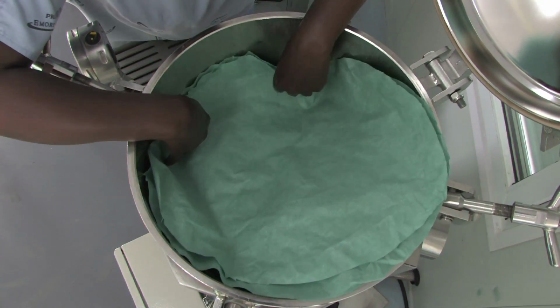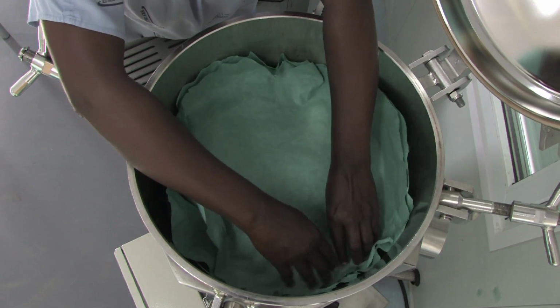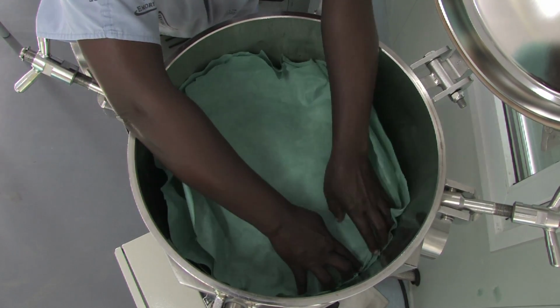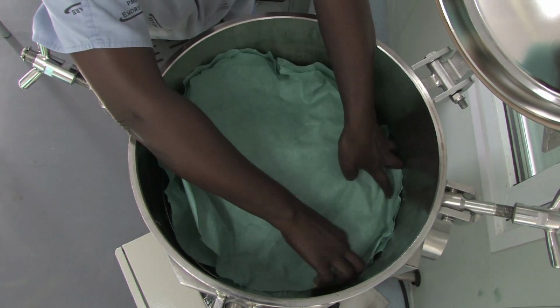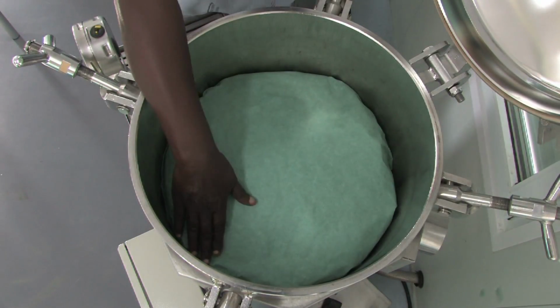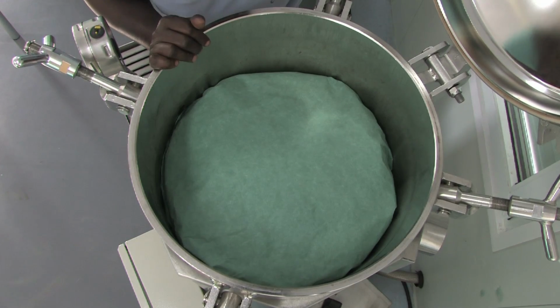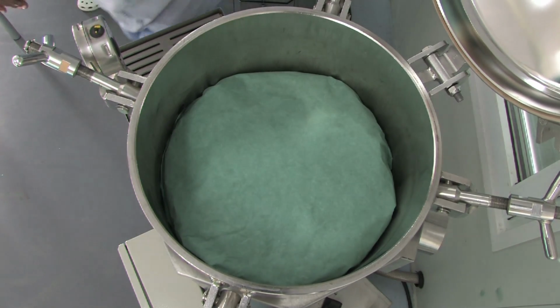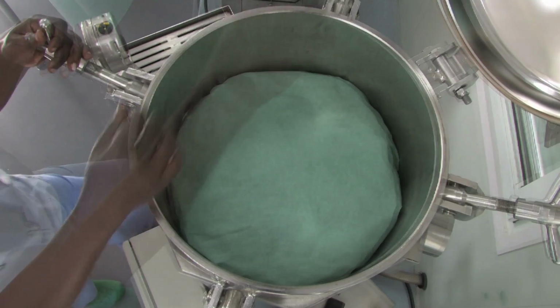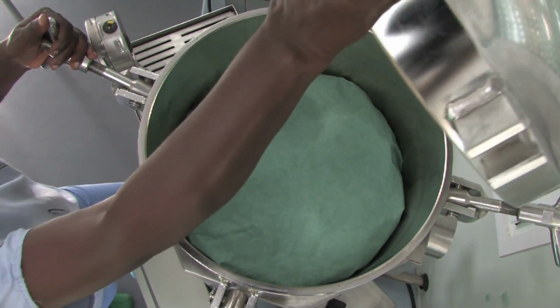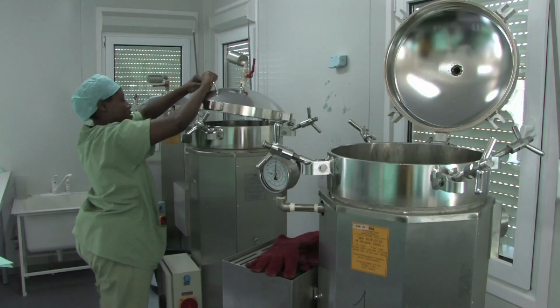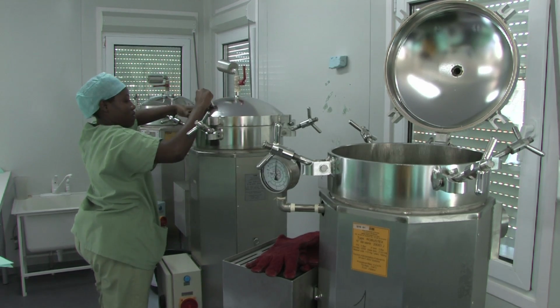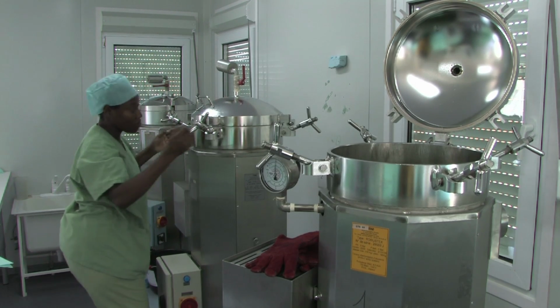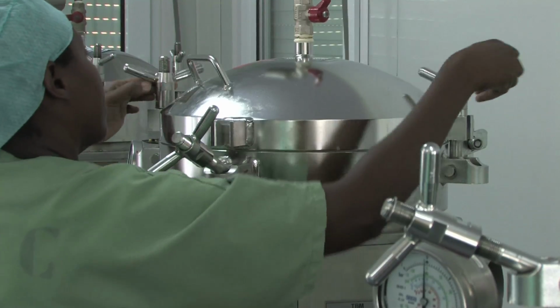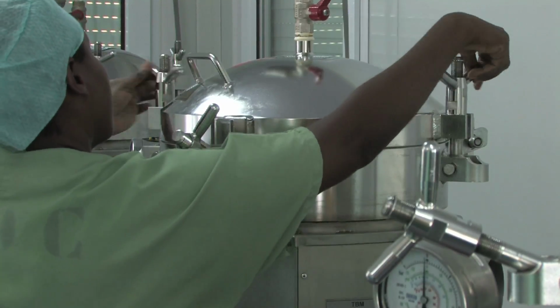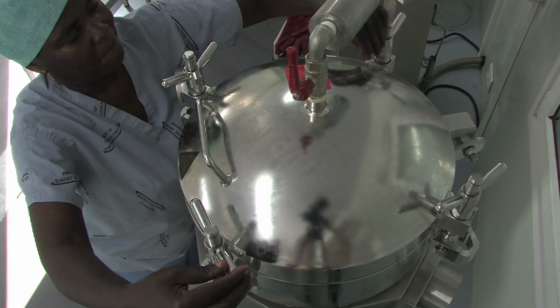5. Cover the top of the upper basket, either with 2 sheets of crepe sterilization paper or with 1 non-woven sheet, which is more waterproof. This prevents the condensation that forms on the cover as the steam cools from falling on the load and wetting it. The condensation will run down the paper and drip down along the walls. 6. Close the cover. Tighten the wing nuts in diametrically opposite pairs so that the seal that keeps the cover watertight is compressed evenly.